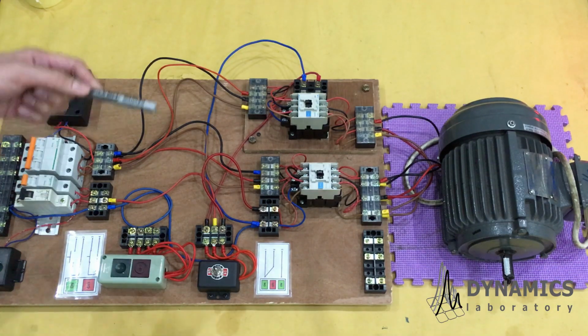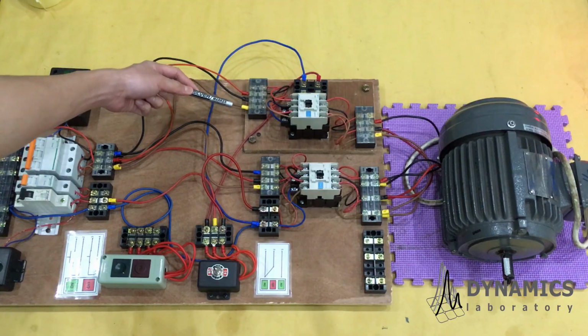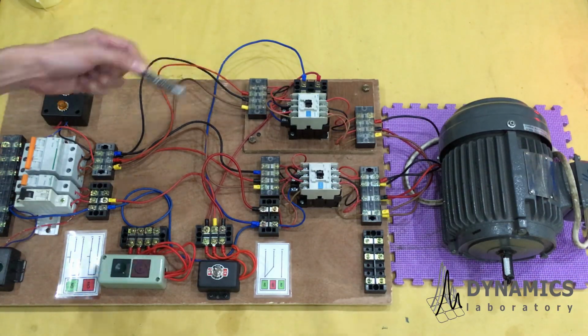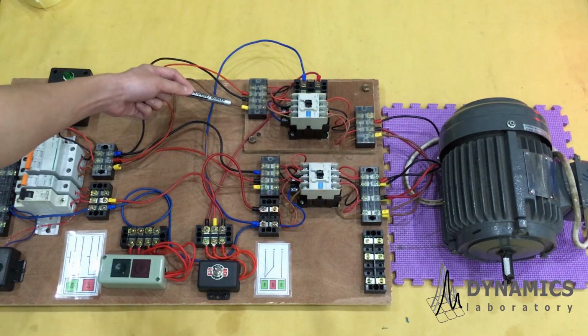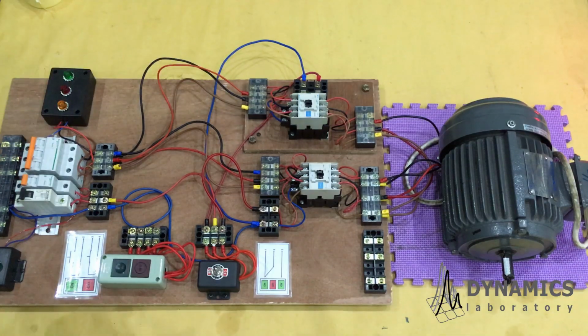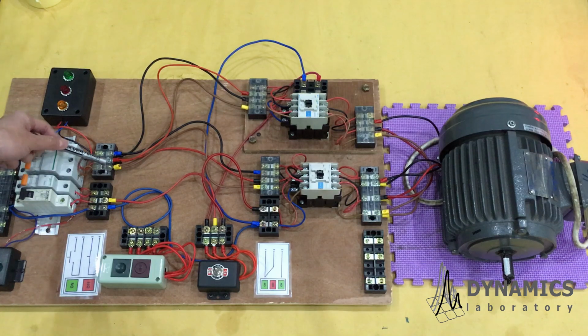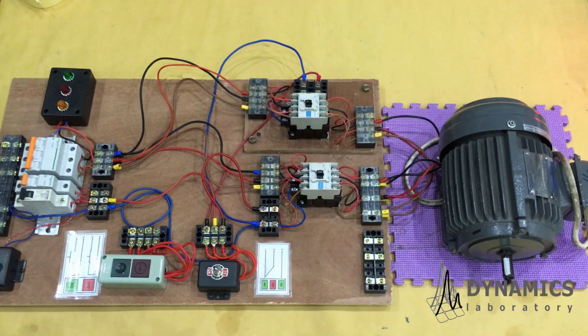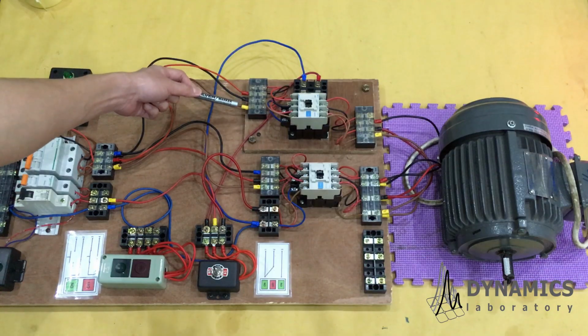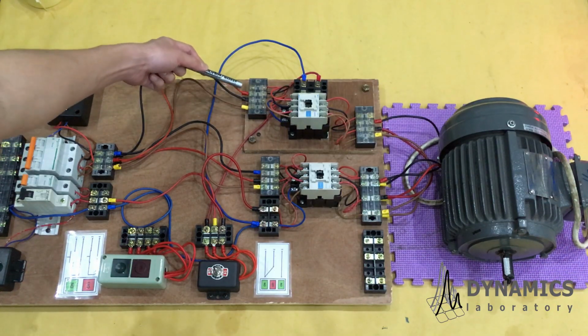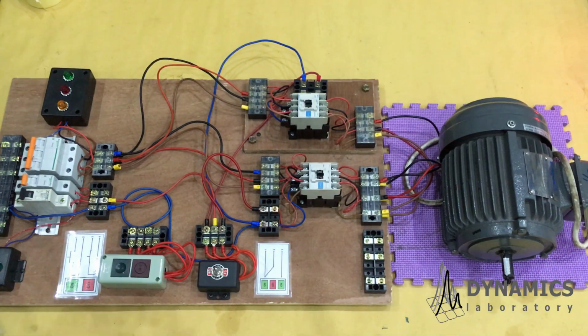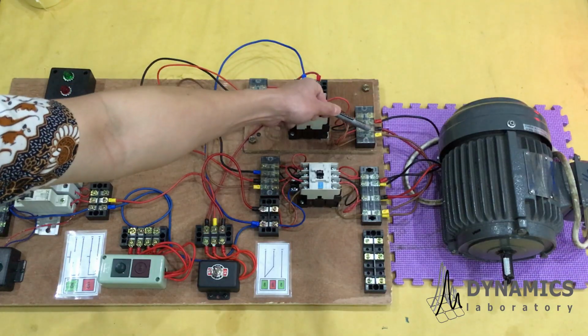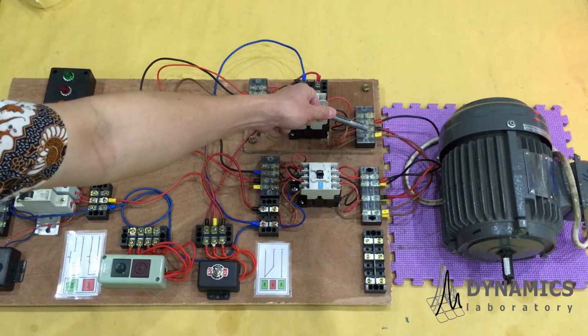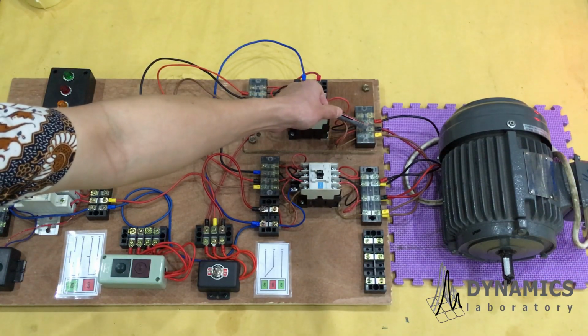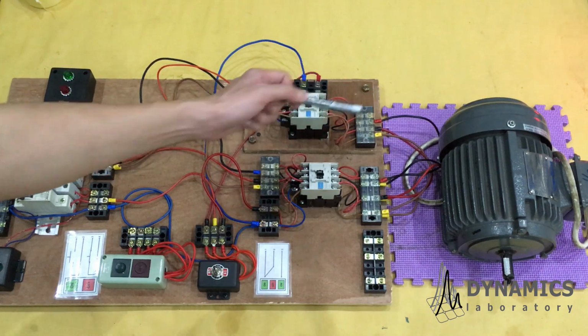Take a look over here. It becomes brown, black, and red, which means R, T, and S voltage line. Remember in here, brown, red, and black means R, S, and T voltage line. But in here, you can see the sequence is different. R, T, and S voltage line. Meanwhile, at the other side of the contactor, coils from three-phase AC motor are the same. Brown, red, and black. U, V, and W.